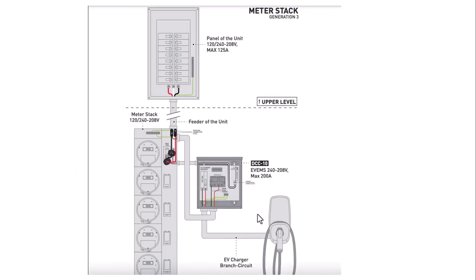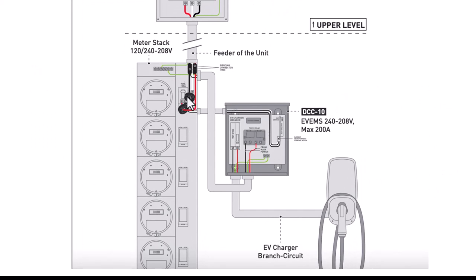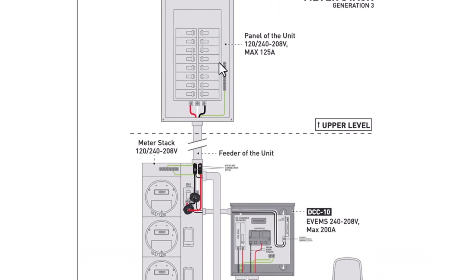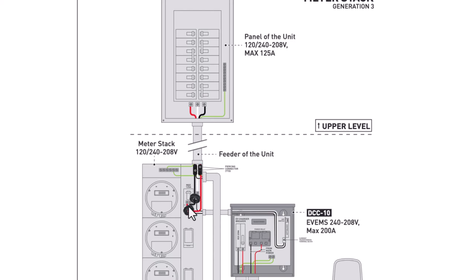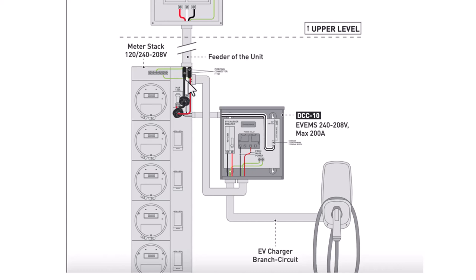And here's another installation example for the DCC-10. You can have it in this type of configuration as well. Basically, it taps off not from the actual disconnect, but it taps off of the main going out with these piercing connectors that basically will tap into the main and then run in exactly to this. And then from the relay, it basically will go to the circuit breaker. And when you do these installations, these are just a typical diagram, but you have to follow your local electrical codes to see if these type of installations are allowed in your local area. And you have to follow all the NEC codes as well as the local codes dealing with the location that you are installing this system at.